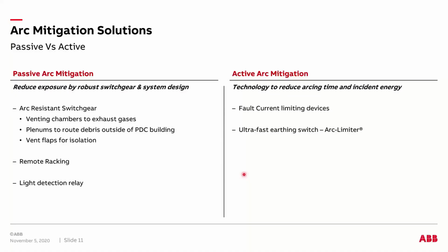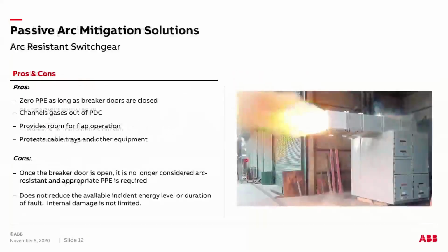You do not have to replace any of the vertical sections. For example, in an arc resistant switchgear, if you have an arcing fault, you are protecting the personnel for a type 2B, like AFLR. But you are damaging your equipment, where you may have to replace one or two sections of your switchgear, whether it's medium voltage or low voltage. That is clearly defined right here. So you can use a 0 PPE or a class 1 HRC rated 1 PPE as long as the breaker doors are closed for an arc resistant equipment, and none of the personnel will be affected.